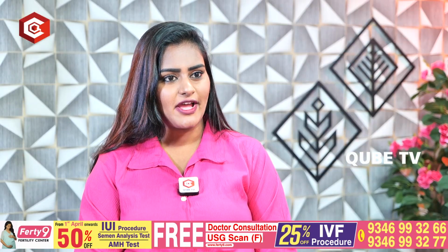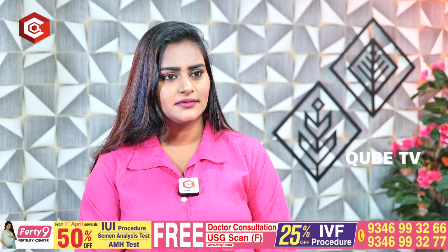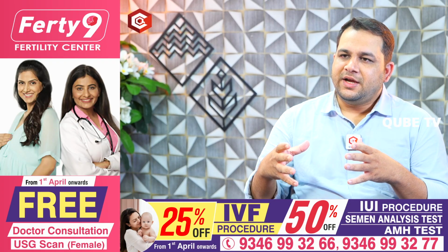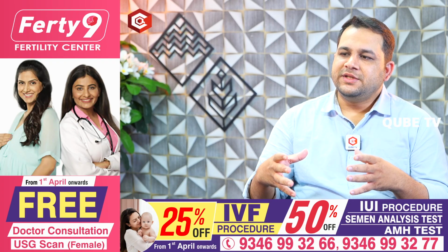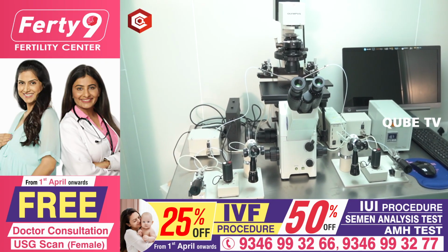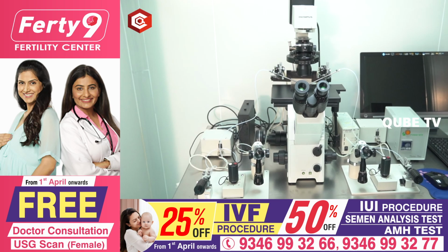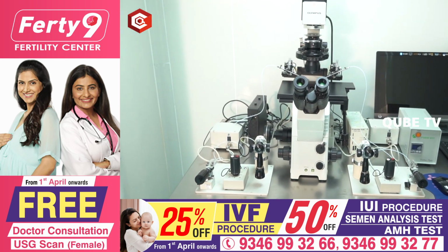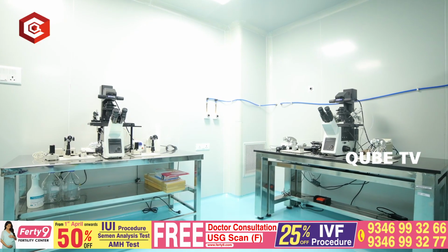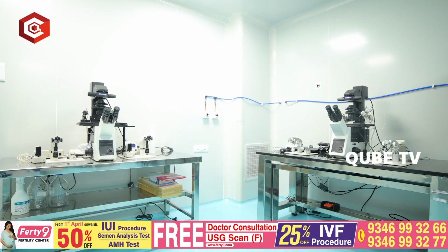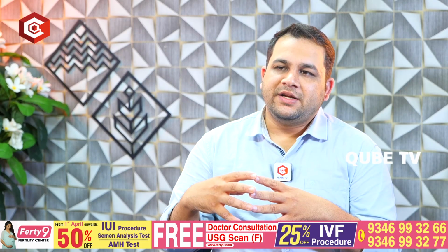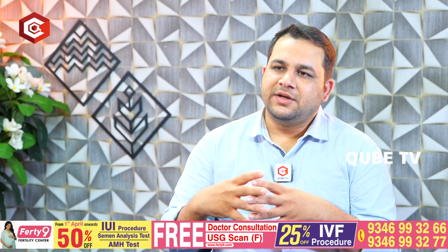So what is an anti-vibration table and how will you use it, sir? The anti-vibration table we normally use for our ICSI machine. Vibration is normally present, and gametes are very sensitive. When we do ICSI we inject with a needle, and without an anti-vibration table it will vibrate, the gametes will degenerate and growth will be less. That's why we use an anti-vibration table for gamete handling.